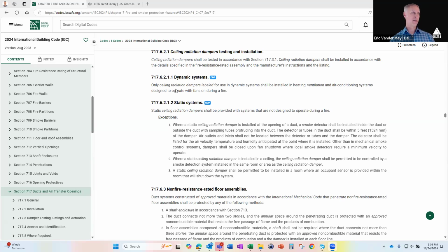Again, there's one or two manufacturers that make these dynamic dampers. And then what was added in the 2021 code was the static dampers. So they actually have provisions that static ceiling radiation dampers shall be provided with systems that are not designed to operate during a fire. And then there's exceptions to that essentially in the code.